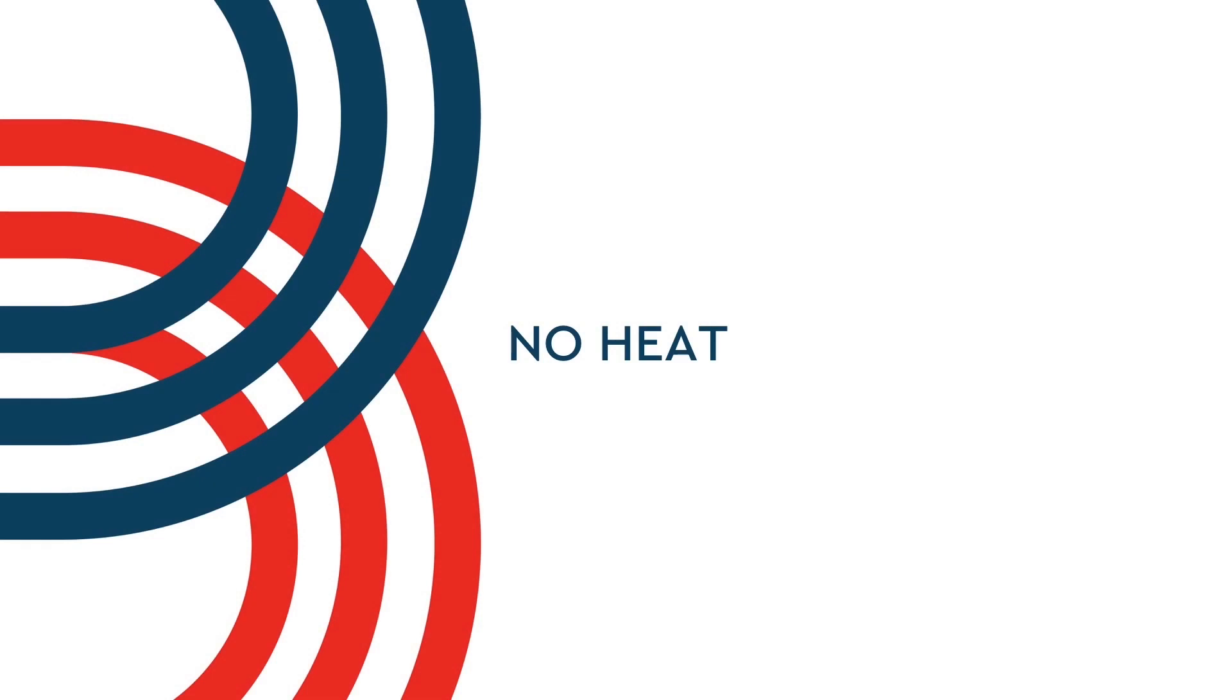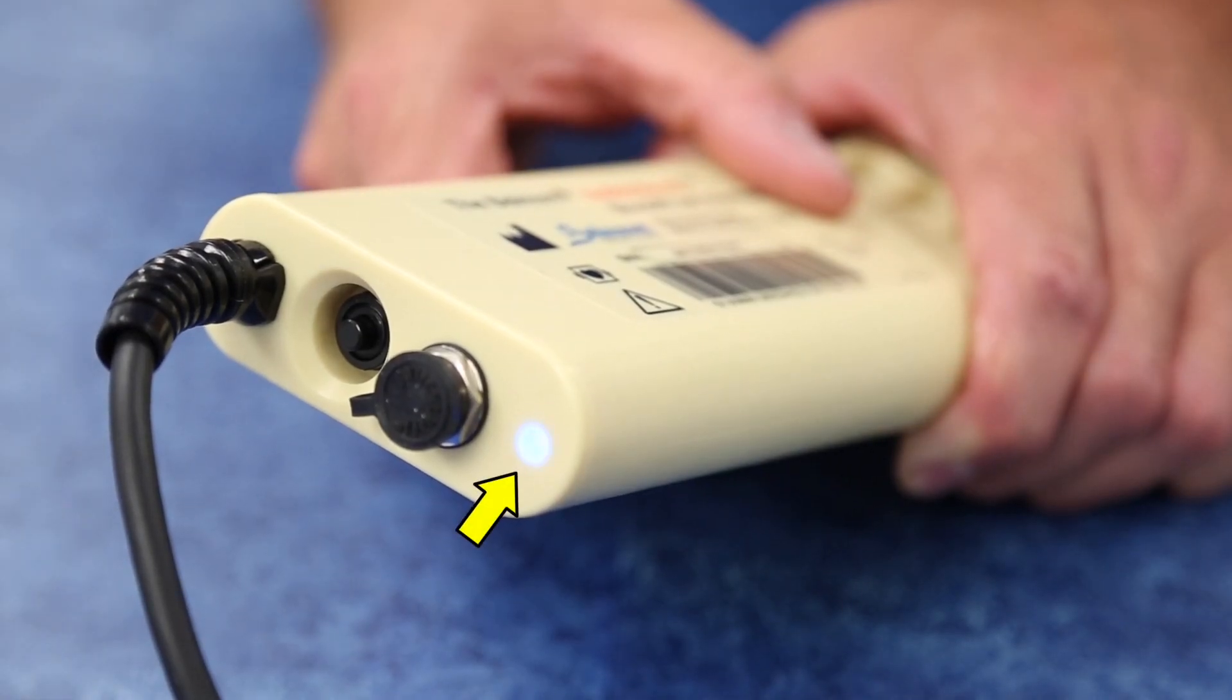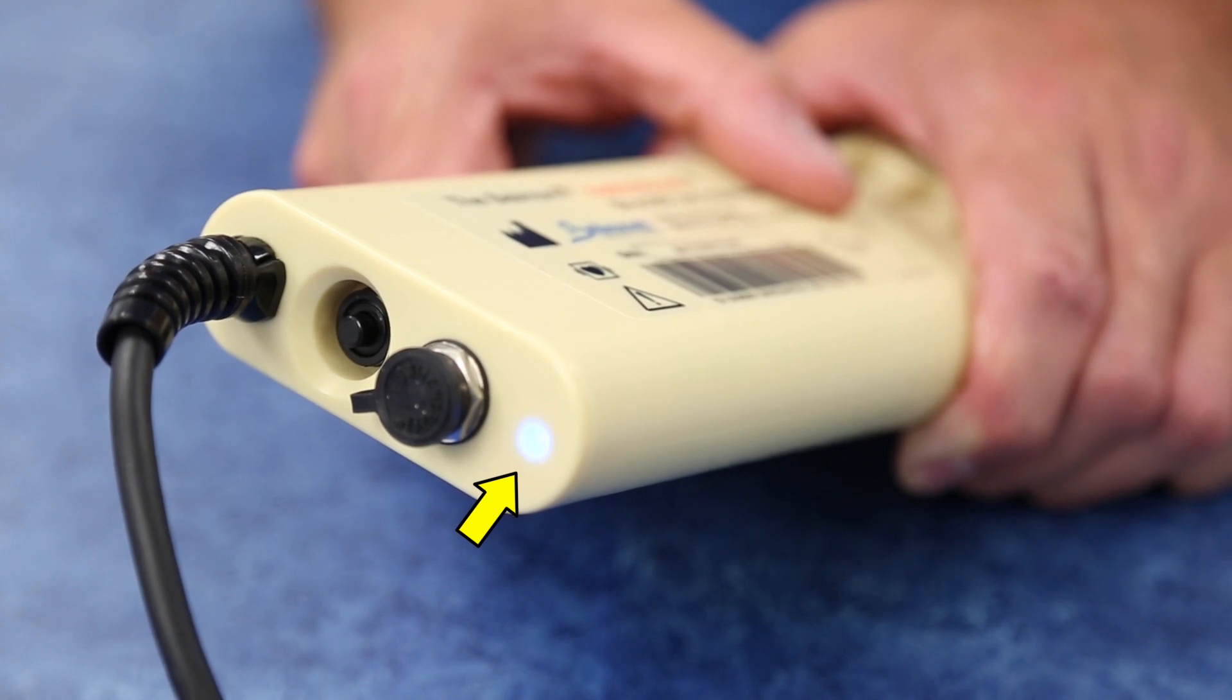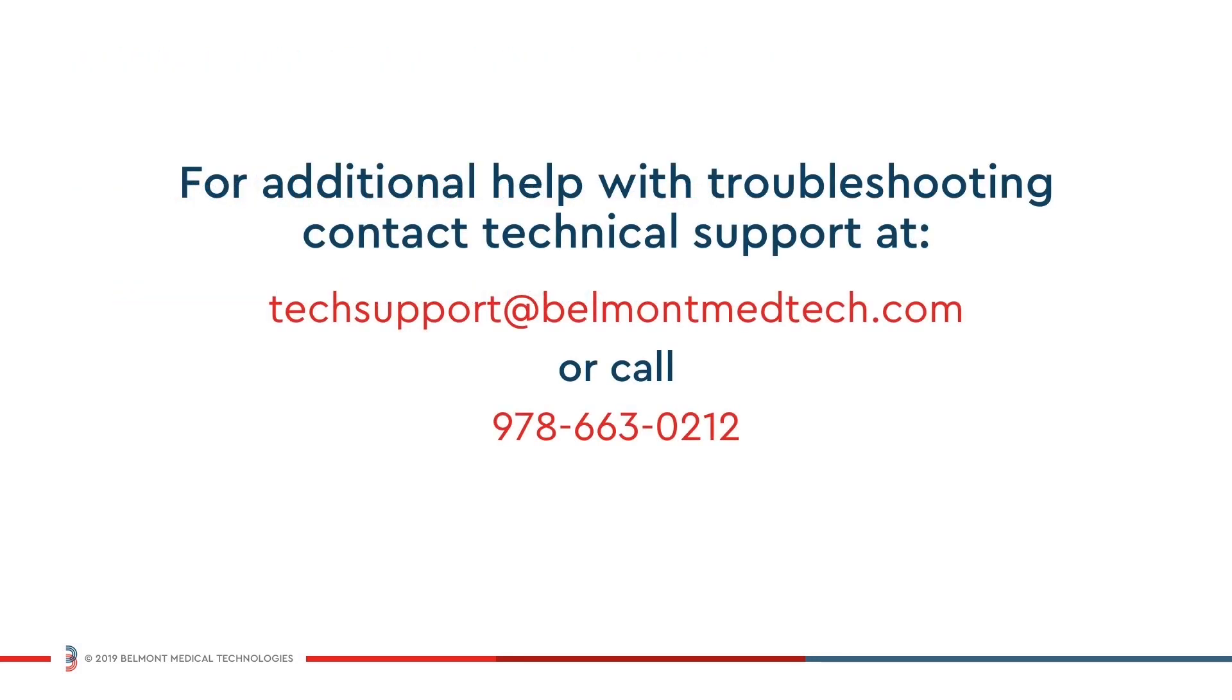If the system detects no heat to the heater plates, blue and red LEDs will flash and an audible alarm will trigger. A no heat alarm may be caused by a failure of the microprocessor or temperature sensor. If the failure reoccurs, please contact customer service for assistance.